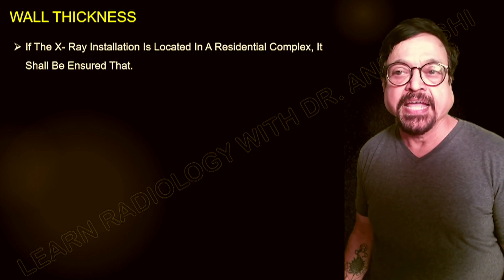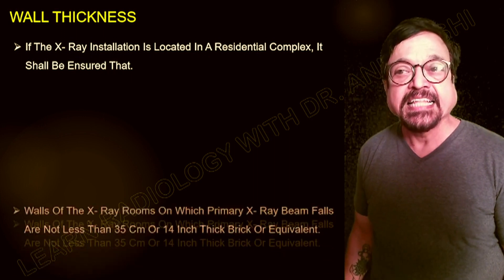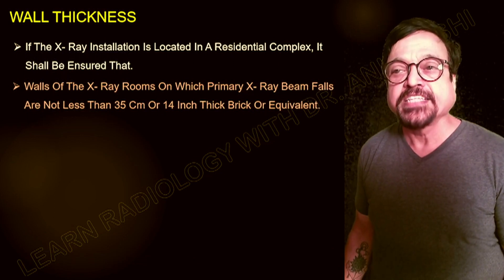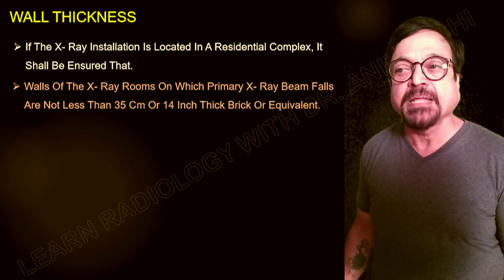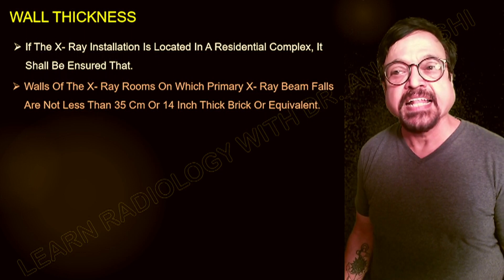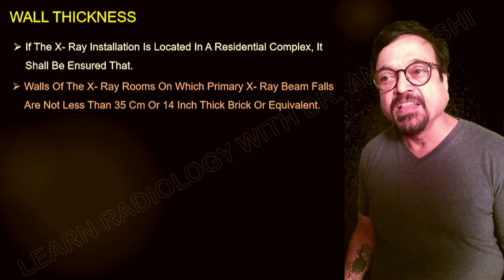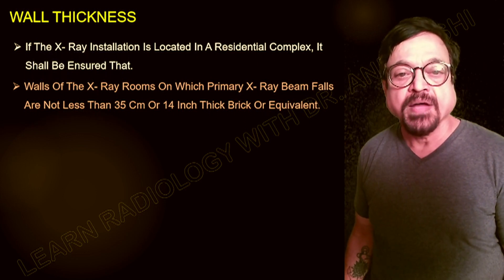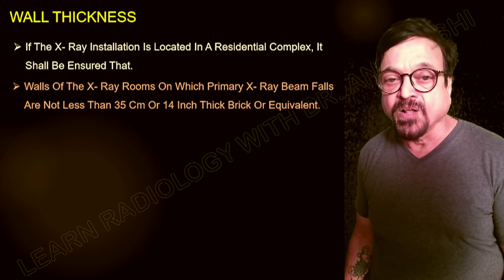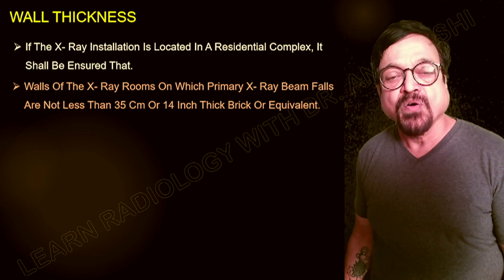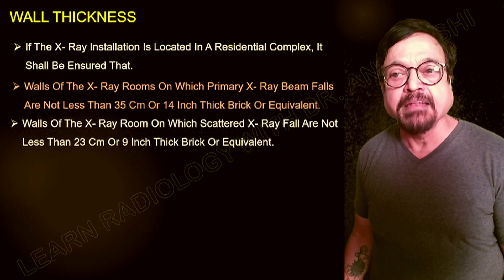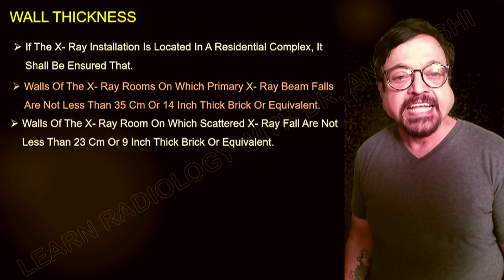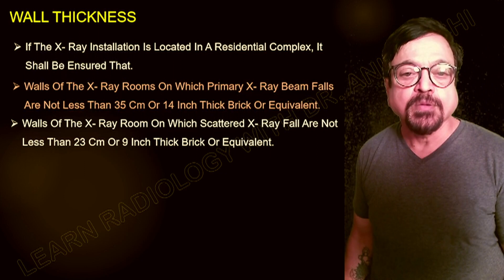If the x-ray unit is located in a residential complex — what we call a non-moving population, such as a residential area or an office — the wall thickness has to be meticulously followed. The walls of the x-ray unit on which the primary x-ray beam falls shall be not less than 35 centimeters or 14 inches in thickness. We divide the room into two parts: where the primary beam falls requires 14 inches, and the remaining walls can be up to 23 centimeters or 9 inches thick.